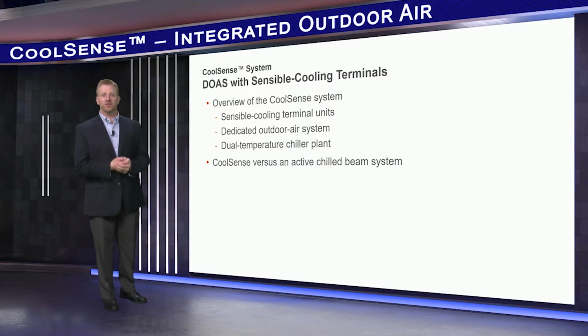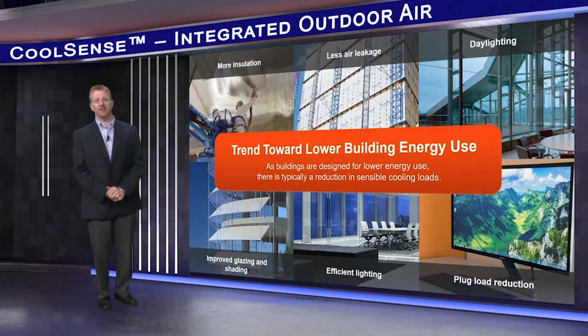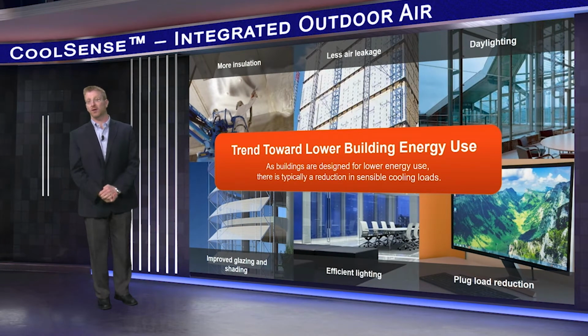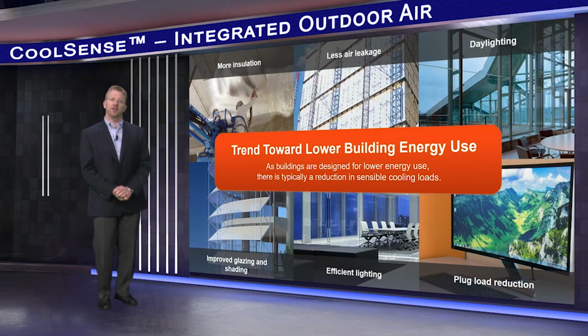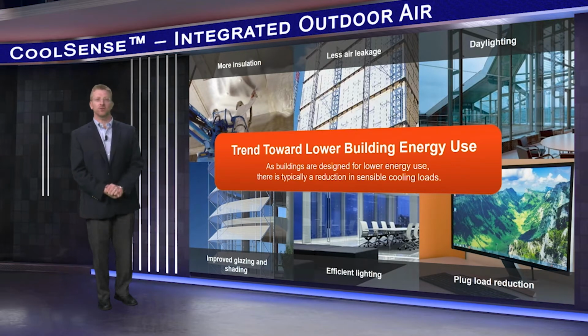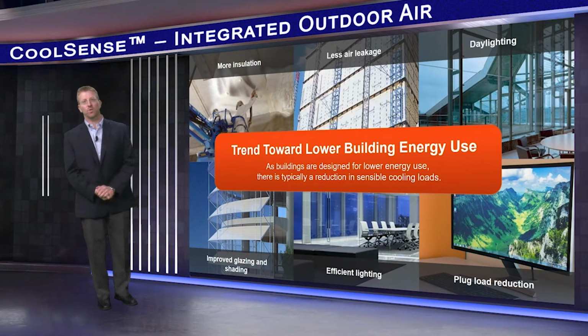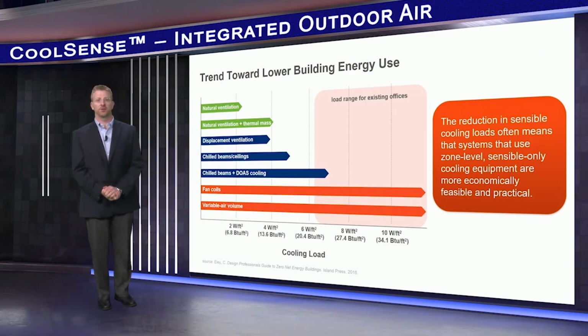But first, let's look at some trends that spurred our interest in developing the CoolSense system. As buildings are designed for lower energy use, there is a correlating reduction in sensible cooling loads. Much of this is due to improved insulation, better glazing or shading, less air leakage, and tighter buildings, more efficient lighting, and even reductions in plug loads. As an example, in many applications, LED lighting is being used instead of incandescent or fluorescent light fixtures. With LED, the electricity use is less, and they also generate significantly less heat. This is one way that sensible cooling loads are being reduced.